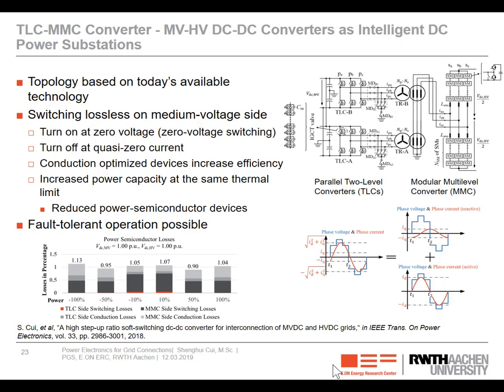So here, the idea is that when these two-level converters are operating in the broken mode like a dual active bridge, the MMC actively controls the transformer current in a sinusoidal form, and it injects a certain small amount of reactive current into these two converters, so that they are turned on at 0 voltage and turned off at very, very small current. So there is almost no switching loss on these two converters. So overall, the DC-DC converter can achieve a very, very high efficiency.